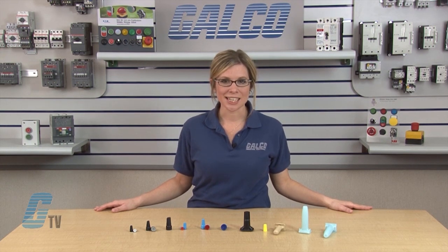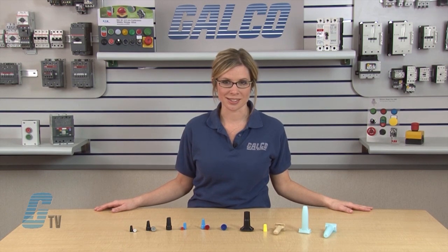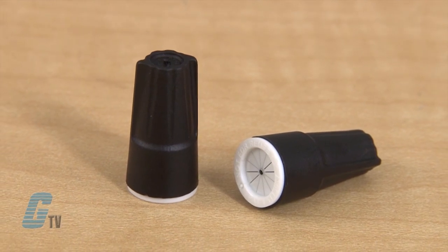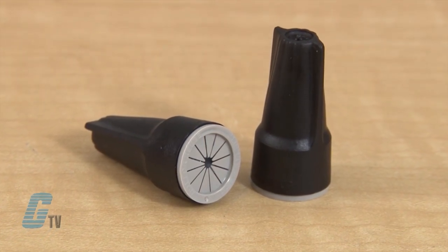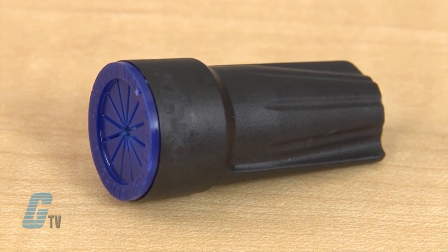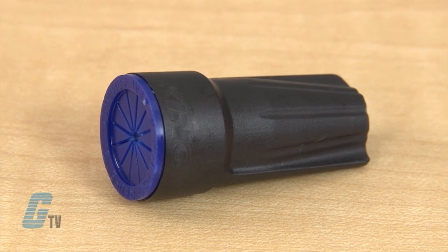The black line is used for irrigation, landscape lighting, and direct burial applications. The black and white connectors are for a minimum 22 gauge and maximum 12 gauge wire. The black and gray connector has a range of 22 gauge to 8 gauge wire. The black and blue connector has a minimum of 14 gauge wire and maximum of 6 gauge wire.